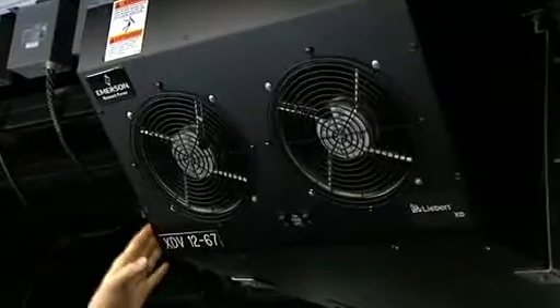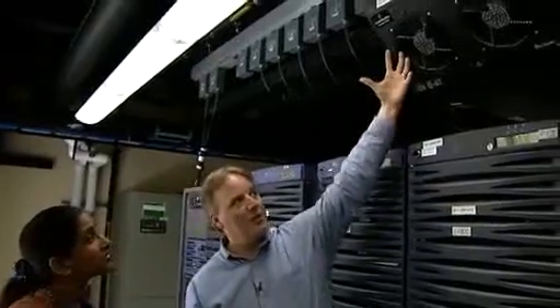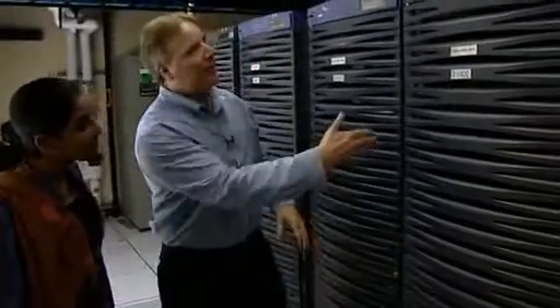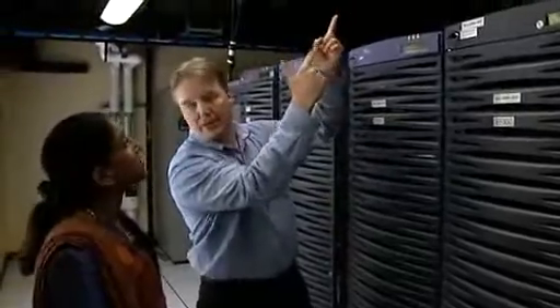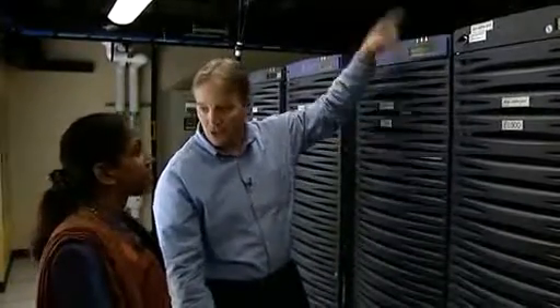The problem is, what happens if you have a 30 kilowatt server next to a 1 next to a 2? You can't cool them all the same way. And so we have deployed closely coupled cooling. And so this is an example. This is a Liebert XD, or extreme density unit, and they call it a Liebert XDV, vertical. And it basically blows cold air out the front. It sucks in the server. The heat comes out the back, and then it returns on the back of the unit. So it now neutralizes the heat at the source.